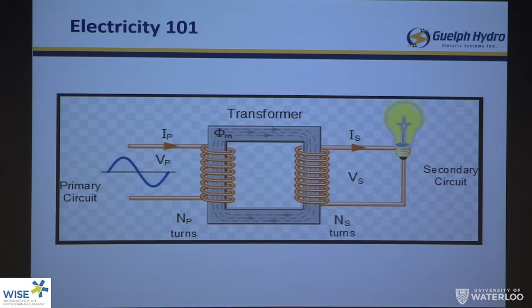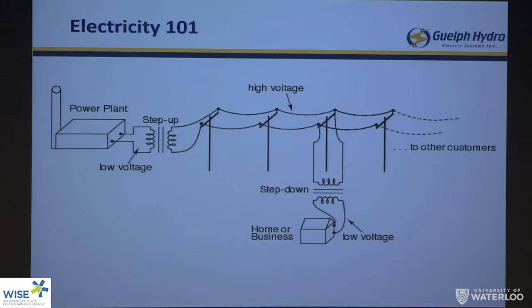Distribution system — we're getting into my area now. We've got transformer stations or generators. High voltage for us is anything from 4 kV up to 44 kV for distribution. Waterloo is 27.6 kV for a lot of the distribution, Guelph is a lot of 13.8 kV, so there are different systems depending on where you are in Ontario. Ontario is a very big system made up of a whole bunch of little systems, and just because of the history of Ontario and electricity, that's just the way it is — a lot of government influence as well.